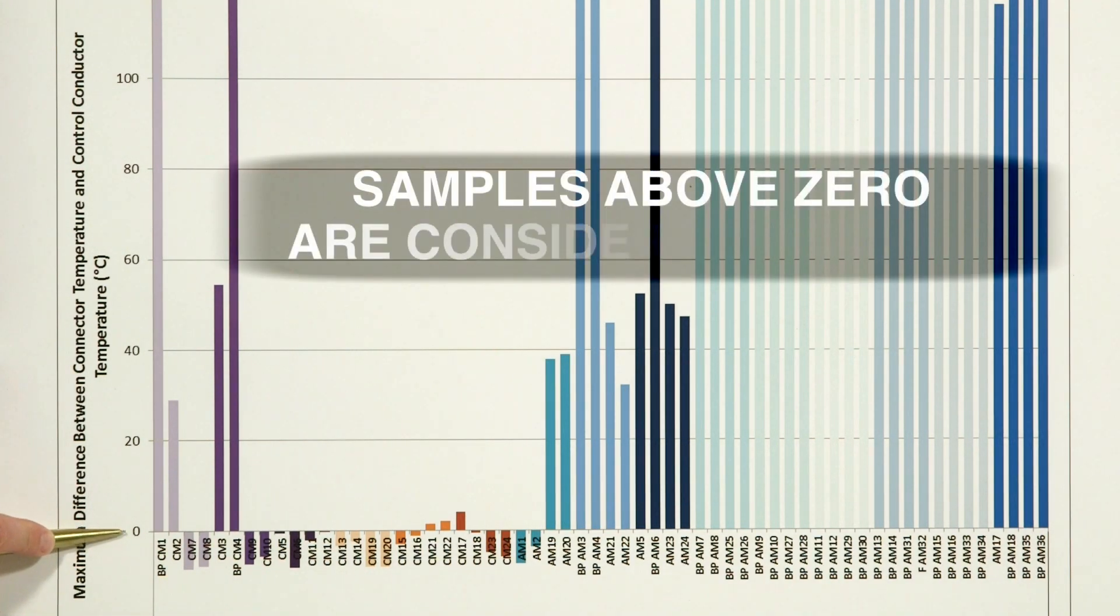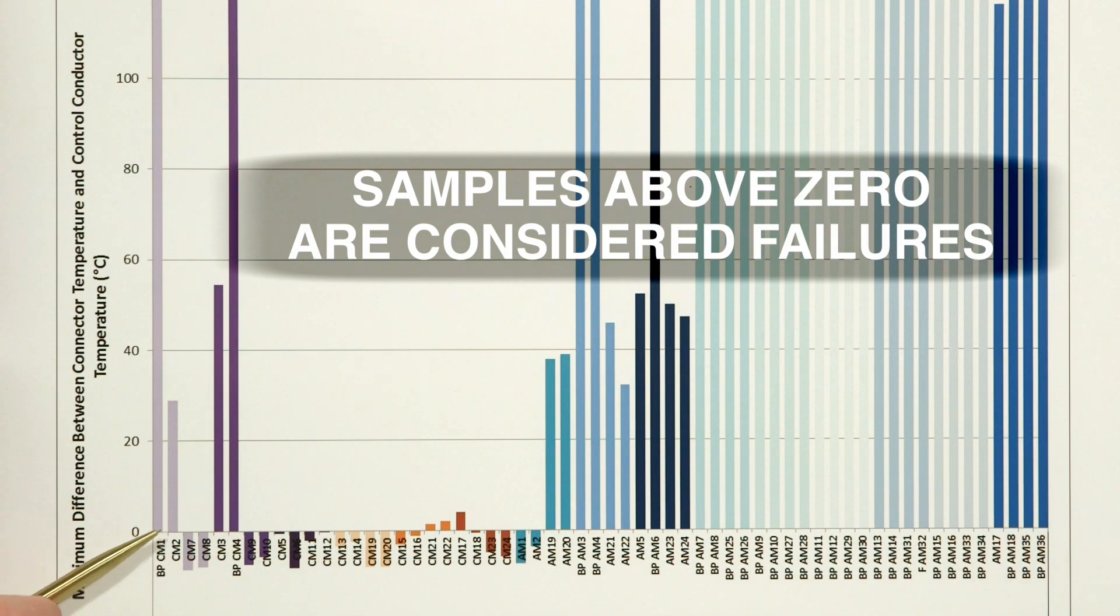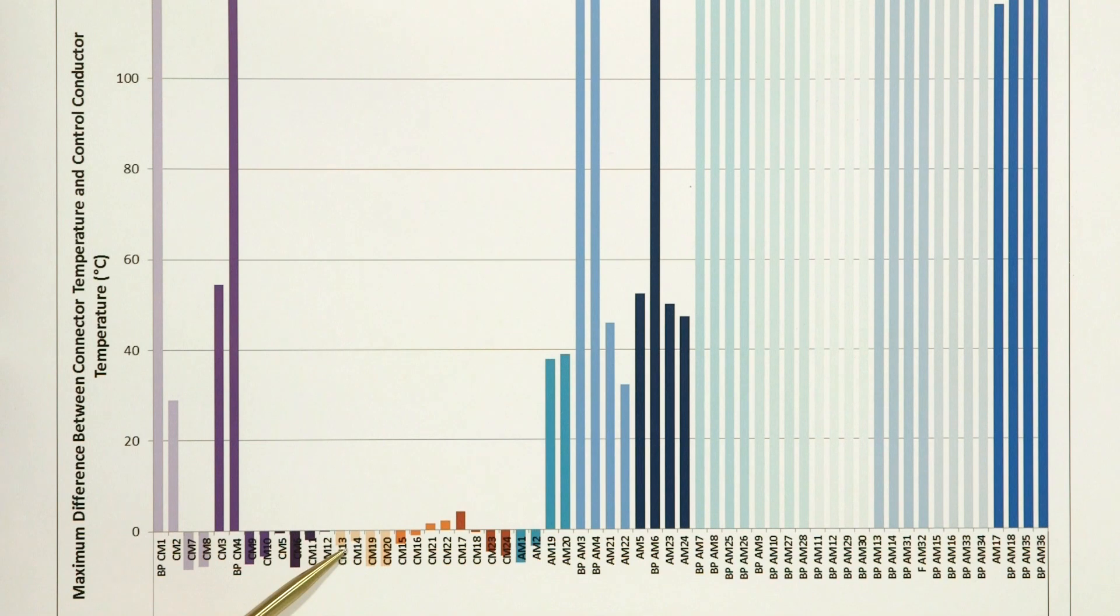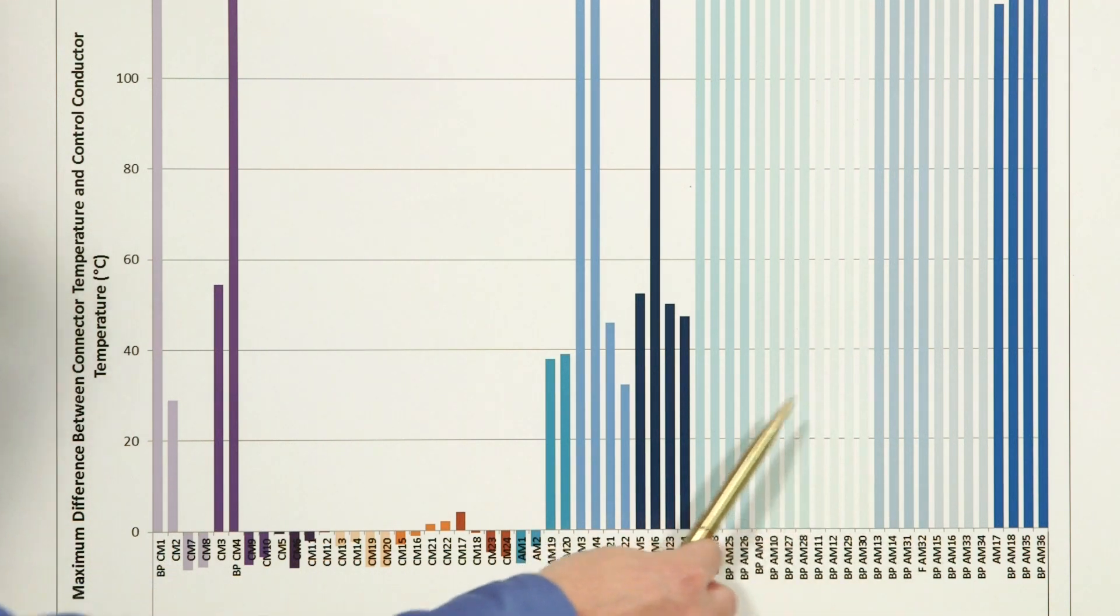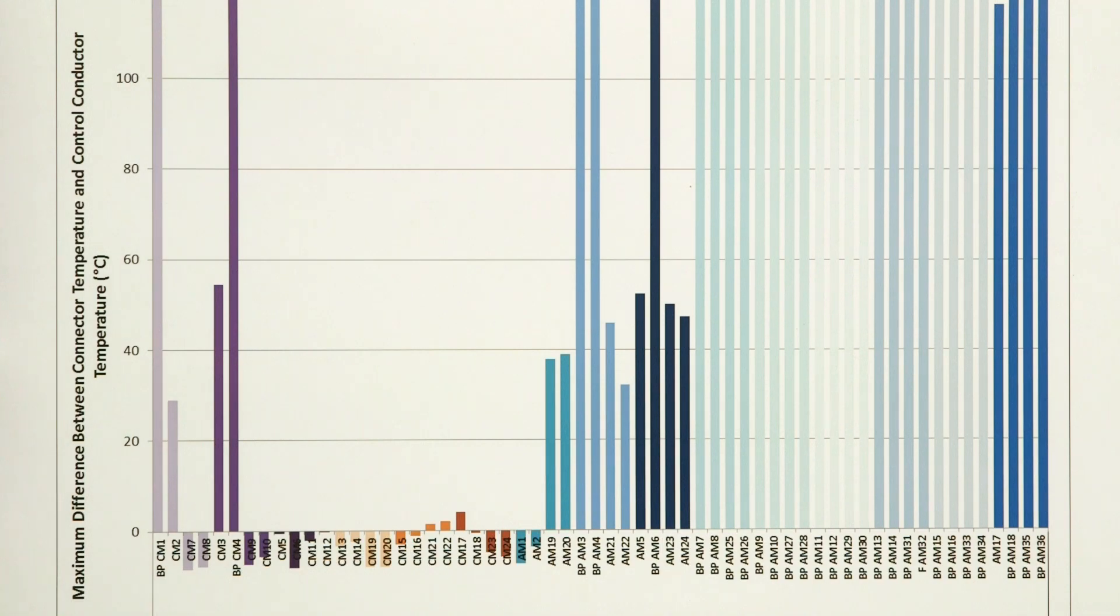As we can see, the samples with copper wire with aluminum connectors have some that are below the control temperature and some that are above. The copper wire samples with copper connectors have the majority that are below the control temperature with a few that are slightly above. With the aluminum wire with aluminum connectors, we have the majority of the samples that are well above the control temperature.